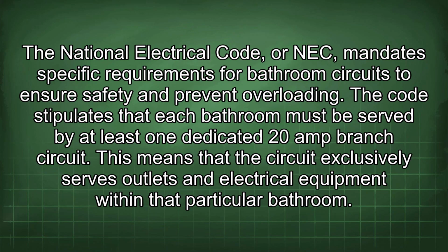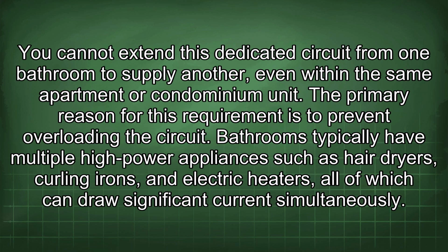The National Electrical Code, or NEC, mandates specific requirements for bathroom circuits to ensure safety and prevent overloading. The code stipulates that each bathroom must be served by at least one dedicated 20-amp branch circuit. This means that the circuit exclusively serves outlets and electrical equipment within that particular bathroom. You cannot extend this dedicated circuit from one bathroom to supply another, even within the same apartment or condominium unit.